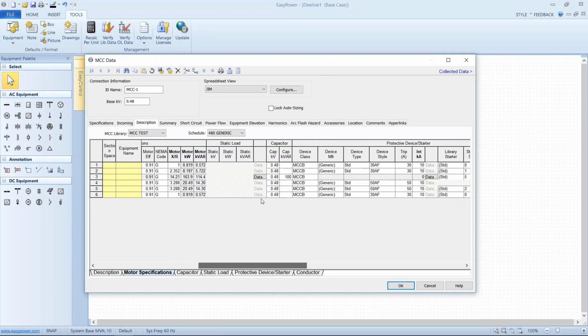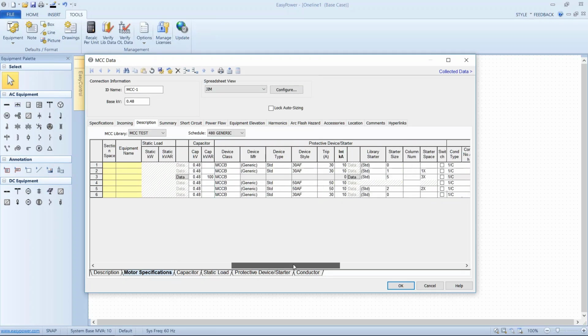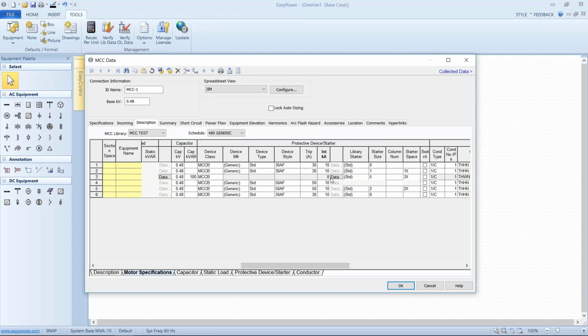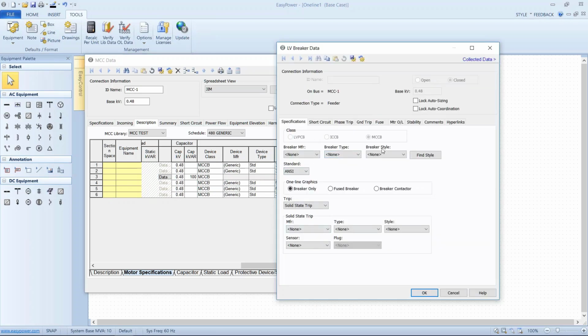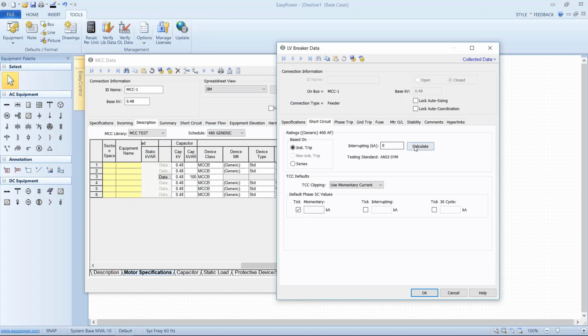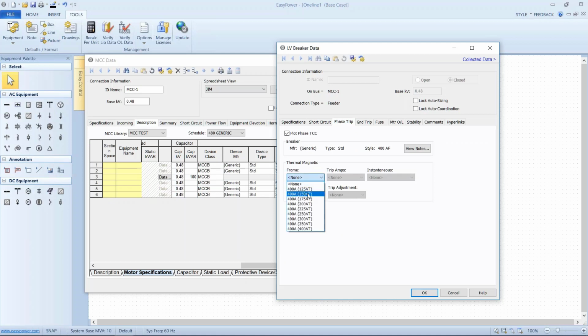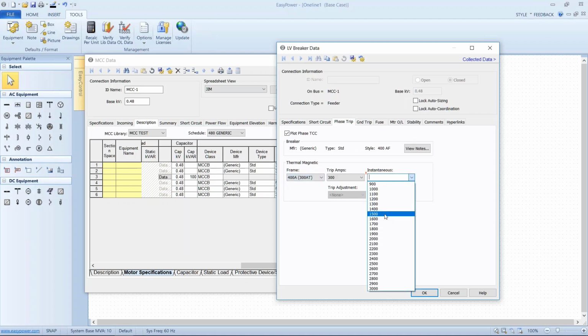Now once I've entered the MCC data, the motor characteristics, I have to do the same thing for the protective device utilizing the data dialog box, and then I would handle this just like I would a standalone breaker. And so we could either use a generic or any type of manufacturer. And again, make sure I use calculate, because this is going to be the interrupt rating that the tool uses when we take on short circuit equipment duty calculations.